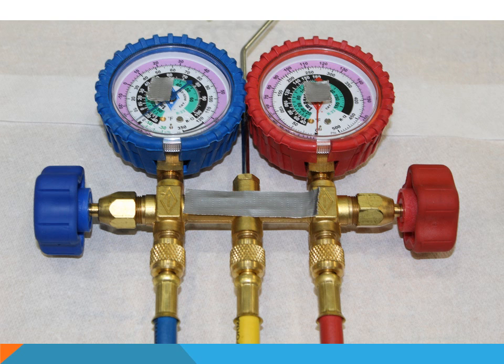These are gauges used in the refrigeration and air conditioning field. They are designed to read pressure, but also the gauge in PSI is calibrated to read the specific temperature of the refrigerant gas based on the type of refrigerant being used — a corresponding pressure matched to that temperature. This is used anytime you need to understand how the system is operating and the refrigerant is flowing through the air conditioning or refrigeration system.